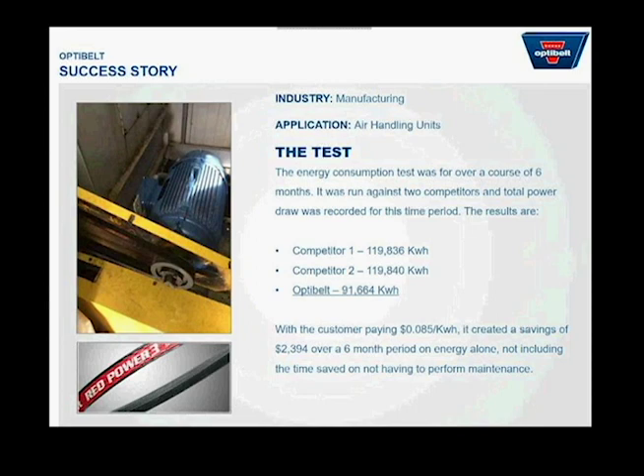With our maintenance-free belts, your preventative maintenance is just making sure the belt is still on the drive, not necessarily that the tension is right. As long as you install it correctly, it keeps going. However, with most belts, you need to retension them every 6 months to a year, or whenever you see some RPM drop in the fan.